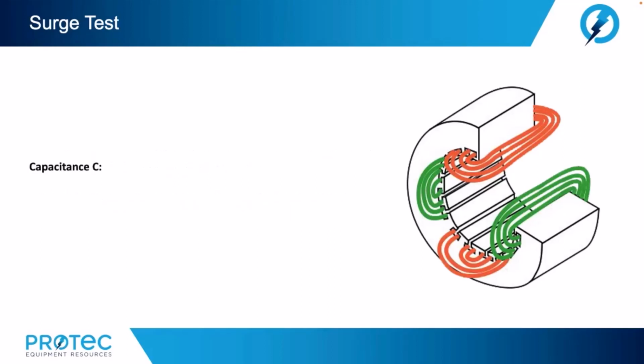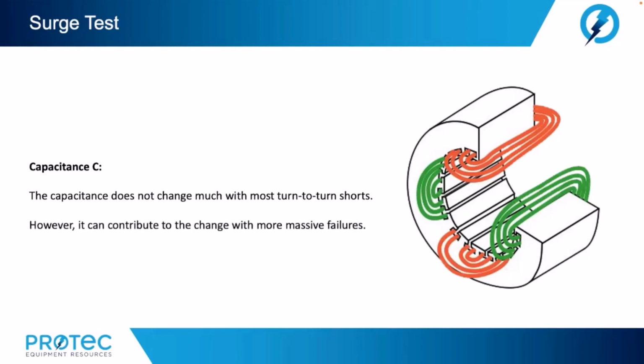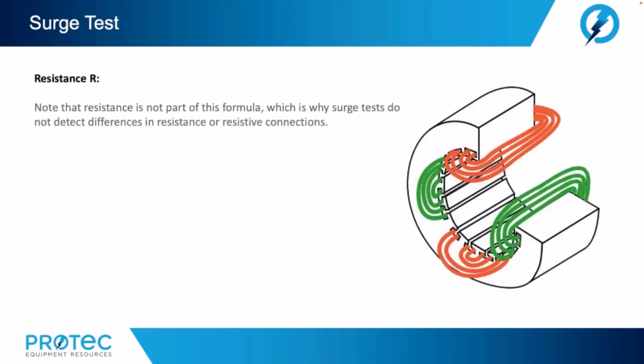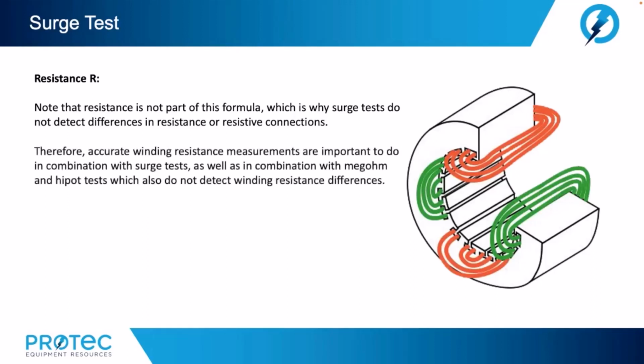Now, let's look at capacitance. The capacitance does not change much with most turn-to-turn shorts. However, it can contribute to the change with more massive faults. Let's look at resistance. Note that resistance is not part of this formula, which is why surge tests do not detect differences in resistance or resistive connections. Therefore, accurate winding resistance measurements are important to do in combination with surge tests, as well as in combination with megohm and hipot tests, which also do not detect winding resistance differences.